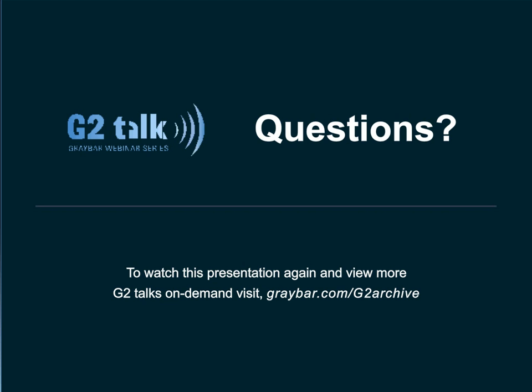Is Class 1 Div 1 the same as Zone 0? I would say that they are similar, but if you were to try an analogy between the class and division system and the zone system, Class 1 Division 1 is similar to Zone 0 and Zone 1. Class 1 Division 2 is similar to Zone 2. But I will say that they are very different standards.